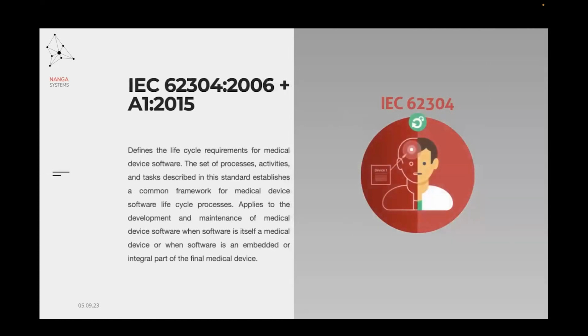So the software as a medical device development is something where we have to comply with IEC 62304. IEC 62304 is a standard that defines the lifecycle requirements for medical device software. The set of processes, activities, and tasks described in the standard establishes a common framework for medical device software lifecycle processes, applies to the development and maintenance of medical device software when software is itself a medical device or when software is an embedded or integral part of the final medical device. So this is the definition of IEC 62304.